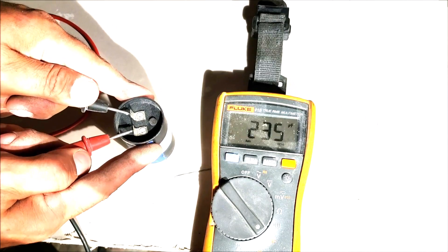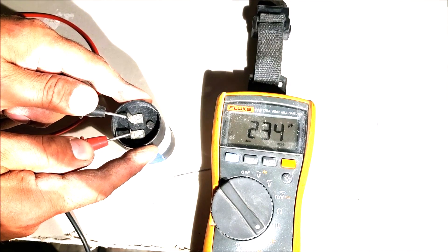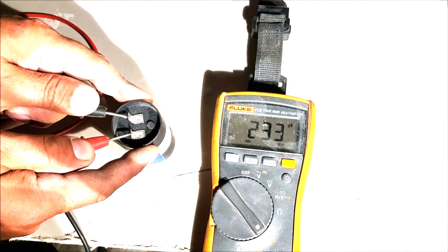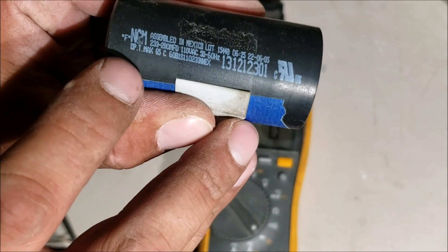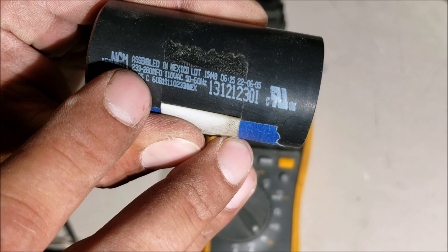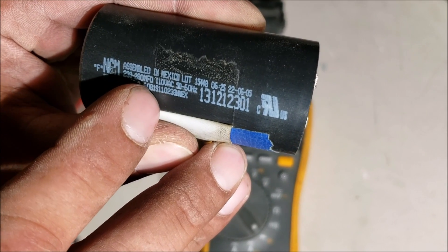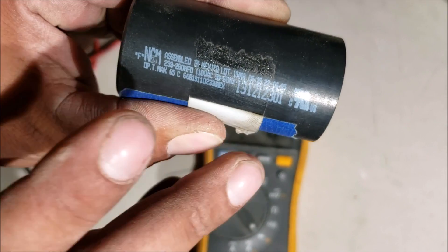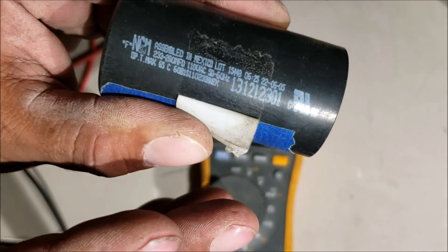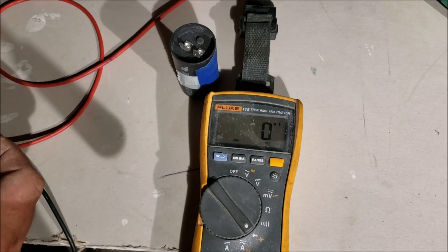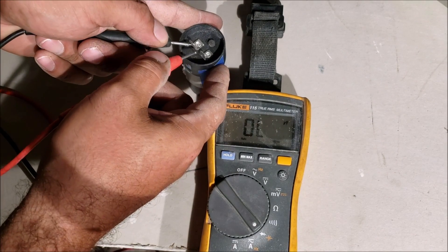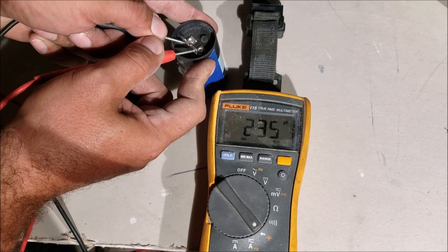You got to look on your capacitor and hopefully the numbers are still there. We're looking for numbers that look like that. We got 233 to 280 mfd, that's microfarads, so that's giving us our range. We have to be in that range for this to be a good capacitor. We got 235, 234, so the capacitor is good.